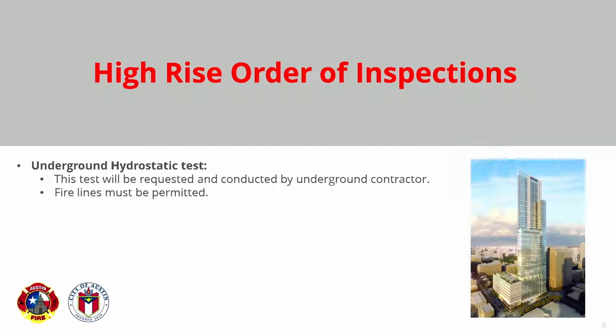For some reason, there's been a number of buildings where, because the connection to city water has been in the right of way, they didn't have to pull a plumbing permit. Prior to us doing the hydrostatic test, we're going to require you to pull a permit for that. So once the piping enters the building, it's required to have a plumbing permit, and it should be specific to the fire line. The description should say fire line in the plumbing permit. Again, that must be permitted.